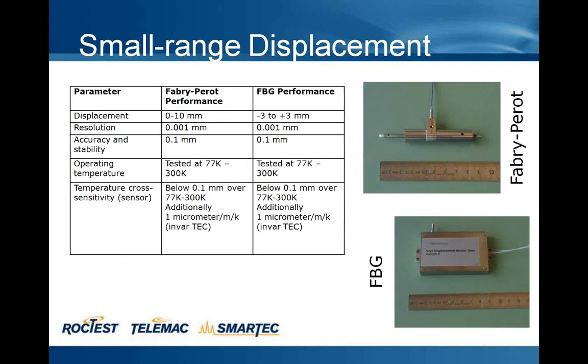First, small displacement sensors. We have Fabry-Perot and Fiber Bragg grating short-range displacement sensors that typically measure movement over a few millimeters — for example plus/minus 3 mm for Bragg grating or 10 mm for Fabry-Perot — with resolution in the micron range. The accuracy is typically 0.1 mm, including all temperature effects over the whole range from room temperature to cryogenic, so calibration curves obtained at room temperature can be applied at cryogenic temperatures as well.